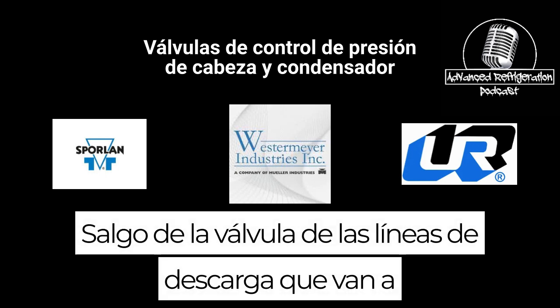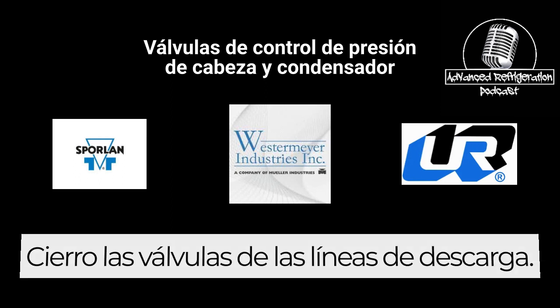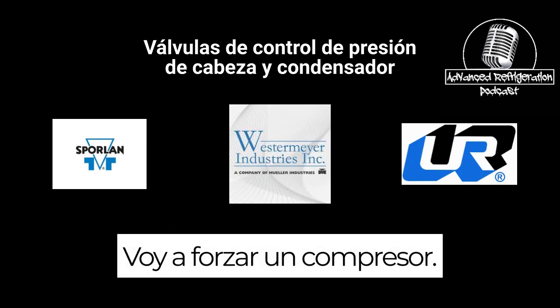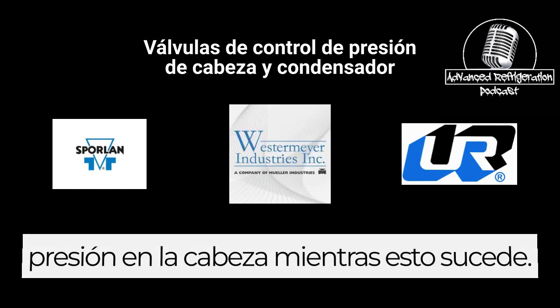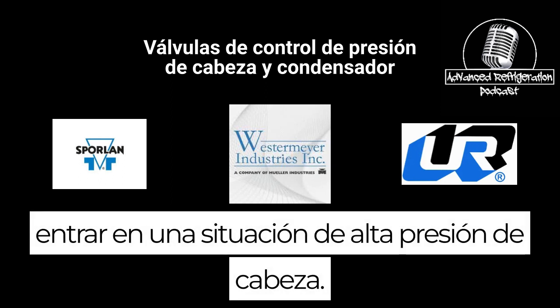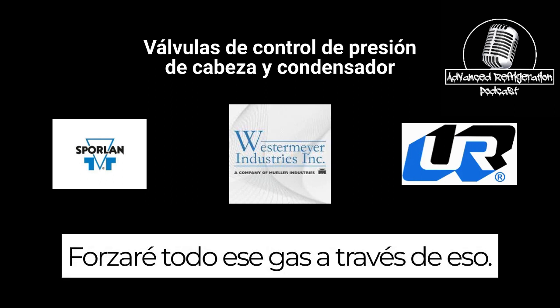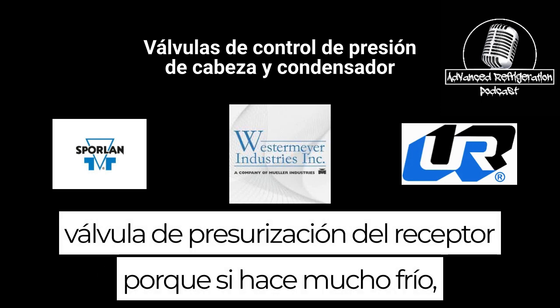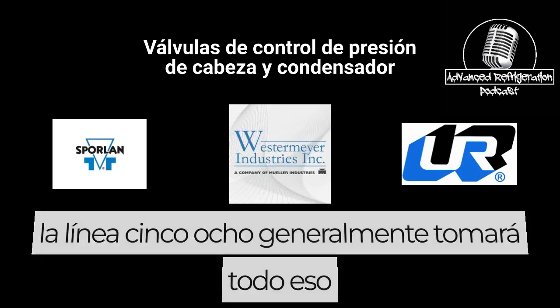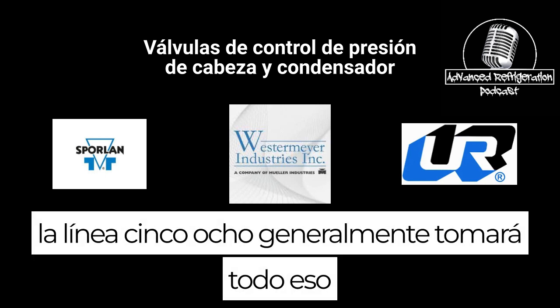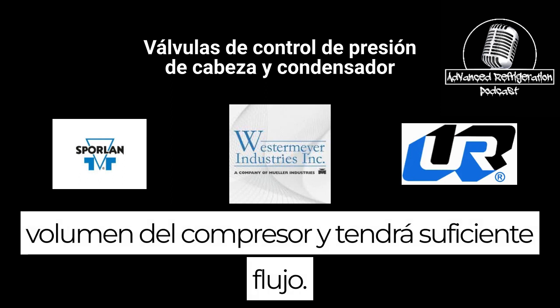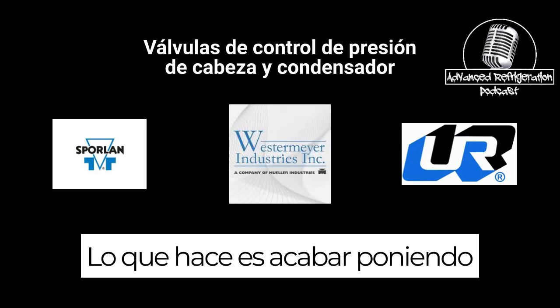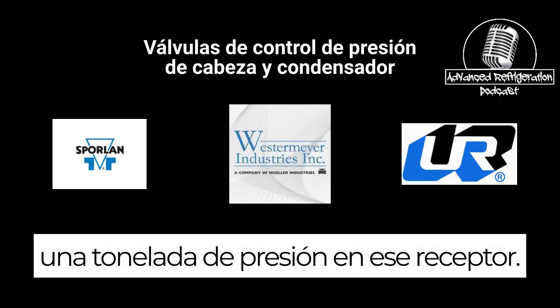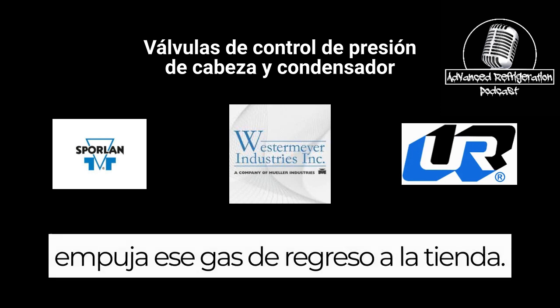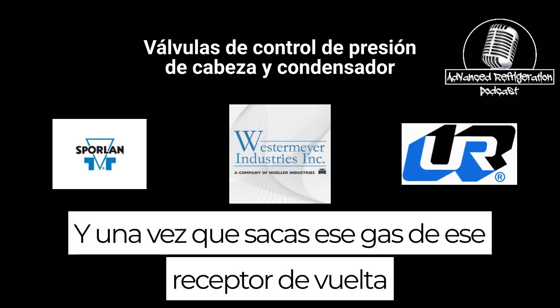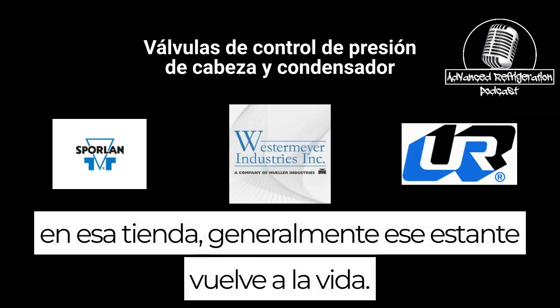I valve off the discharge lines going to the condenser. On the split and full side, I valve off the discharge lines. I will force a compressor on, and you need to be watching your head pressure while this is going on. Just make sure you're not going to enter a high head pressure situation. I will force all that gas into that receiver pressurization valve. Because if it's super cold, a 5/8 line will generally take all that compressor volume and it'll have enough flow. It ends up putting a ton of pressure in that receiver. It warms that receiver up real quick and pushes that gas back into the store. Once you push that gas out of that receiver back into that store, generally that rack comes back to life and you can watch your head pressure.